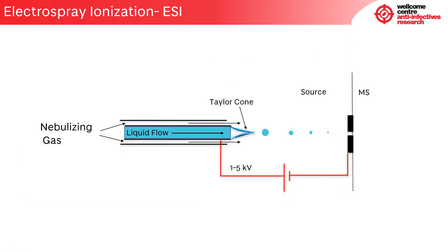The electrospray process is stable only at relatively low flow rates, typically 10 to 20 microlitres per minute. To make the process more compatible with the flow rates typically used in HPLC and UPLC, a nebulizing gas, usually nitrogen, is used which flows concentric to the capillary needle. The gas is believed to reduce droplet size at higher flow rates and therefore increases the efficiency of ion transfer into the gas phase.